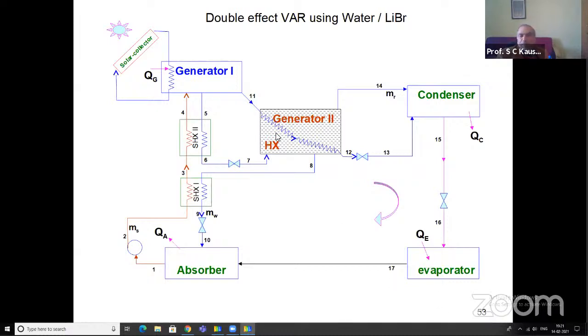So the system is very effective, but you can see that we now have three operating pressures. One is the pressure in the absorber and the evaporator. Another is the pressure in the condenser and generator 2. Another is the pressure in generator 1. So three pressures are there: high side pressure, intermediate pressure, and low side pressure. Just by providing this heat exchanger, we have two heat exchangers, but in a single stage we have only one. The cost of the heat exchanger is not much, so there is no significant additional cost, but the system can provide a COP nearly twice as compared to the single stage system.